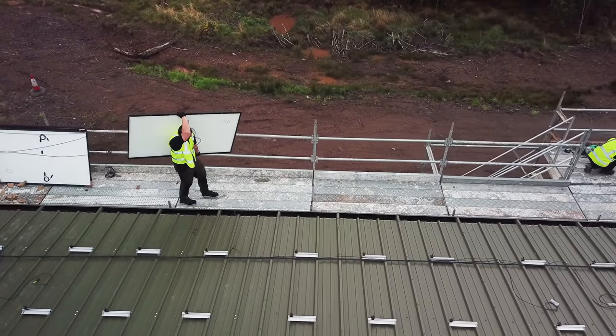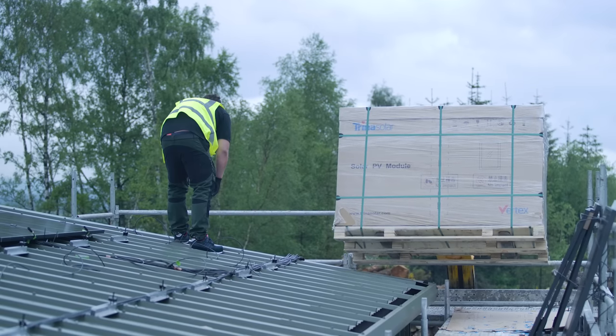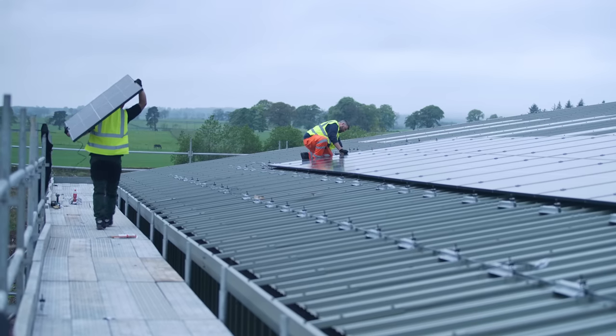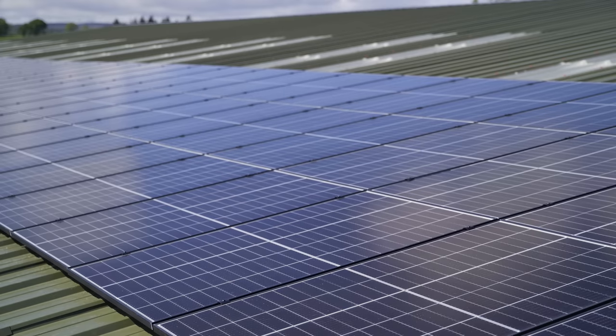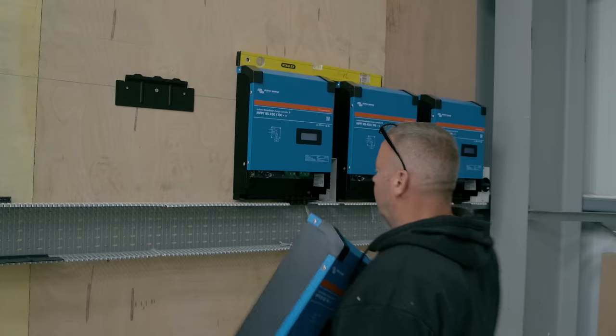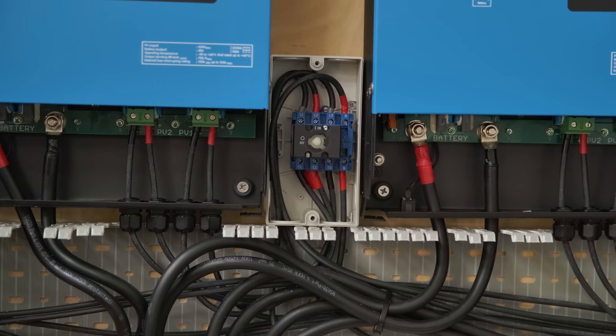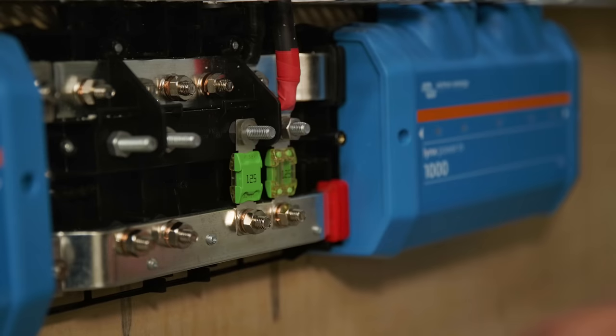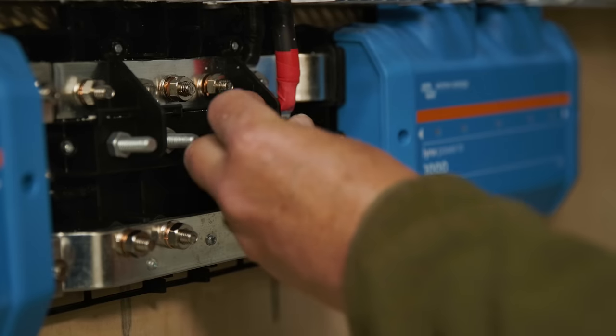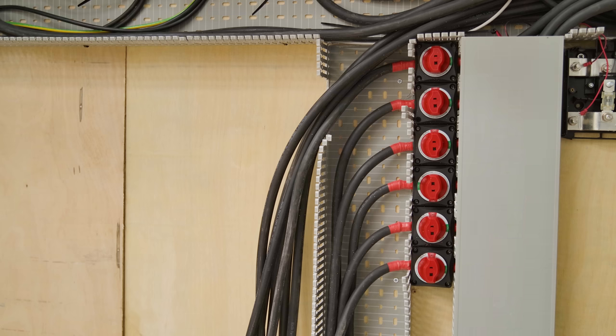On the roof, Off-Grid Engineering are installing 43 kilowatts of monocrystalline panels. Each 400-watt panel is mounted in portrait in three rows, totalling 108 panels. The cabling is brought down the side of the building and into the electrics area. The solar is brought through a disconnect switch and into a Victron Energy MPPT-RS 450-volt 100-amp Smart Solar charge controller, then fused in a Lynx distributor ready to go to the battery bank. The batteries — 91 kilowatt hours of BYD lithium iron phosphate — will be delivered in a second install stage.